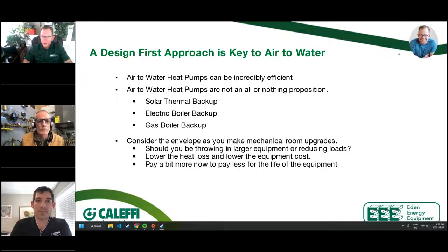So, as we look at it, we always want to make sure we have a design first approach when it comes to air to water equipment. Again, don't try to pigeonhole something into something it shouldn't do. An air-to-water unit can be incredibly efficient, but it depends on whether we actually worked from a design, or we just go to site, drop everything on there and try and figure it out. If you're a really good installer, you can get through it. But the reality is a design-build application is going to be more cost-effective because you're not wasting hours on site trying to figure out how it's all going to go together, regardless of skill level.